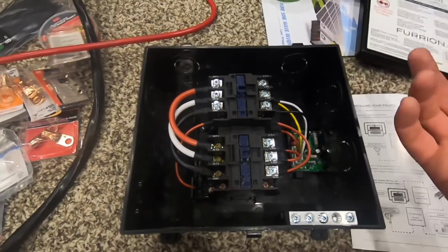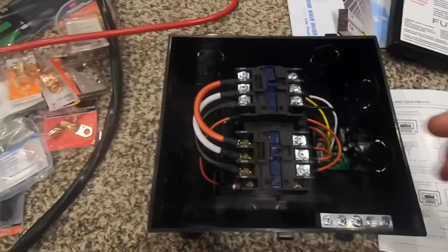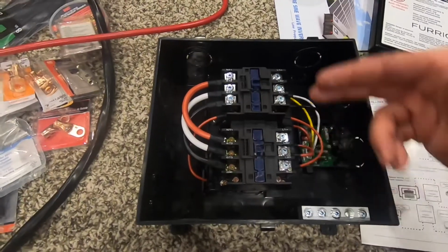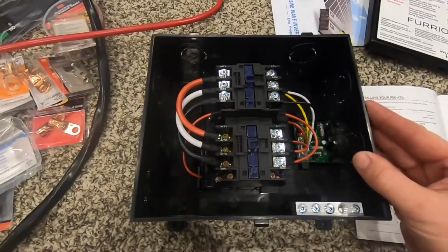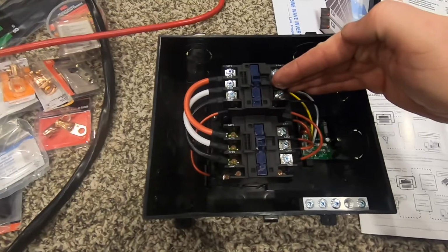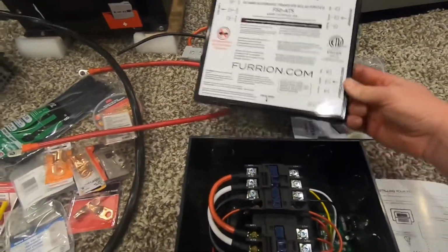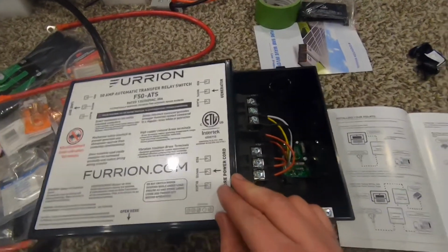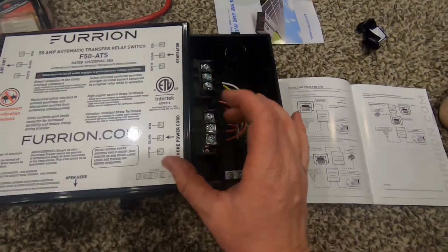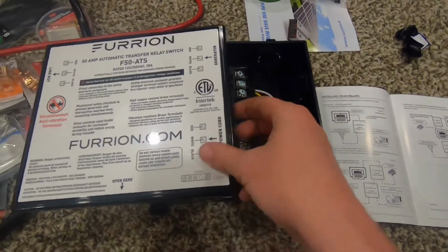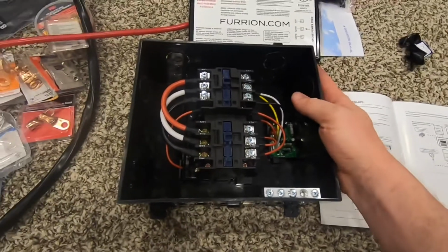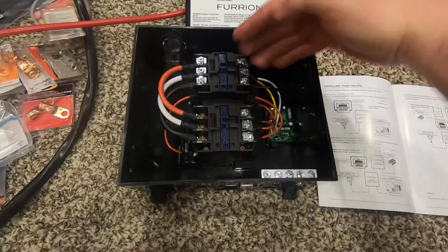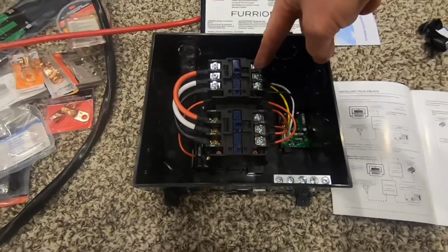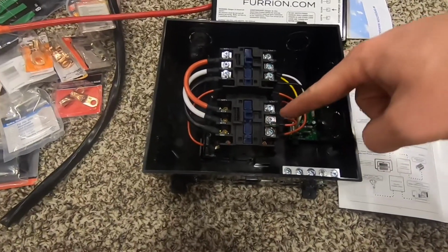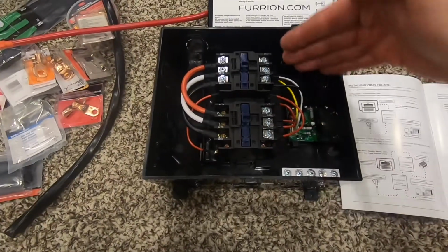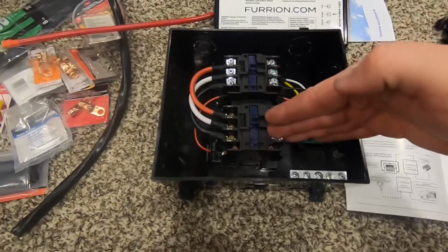When I connect to shore power at an RV park, I want it to switch off the inverter and my batteries and go to the shore power. So what I'm probably going to end up doing is wire it backwards, as shady as that sounds. I'm going to wire my shore power into the generator input, and I'll put this here so it makes more sense, right here. So I'm wiring my shore power on the generator terminal and my inverter on the shore power terminal. Since the automatic transfer switch is generator priority, this terminal is the priority, so that's where shore power goes, and since this is secondary, that's where the inverter goes. That way every time I connect to shore power, it automatically takes that one and puts my inverter to rest.